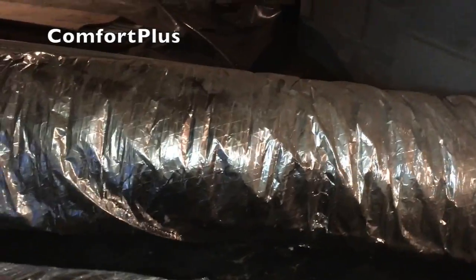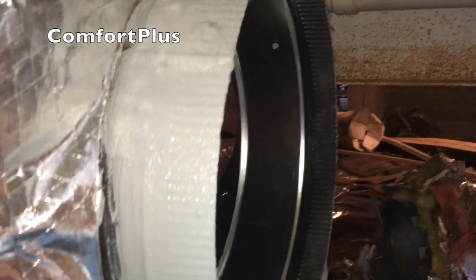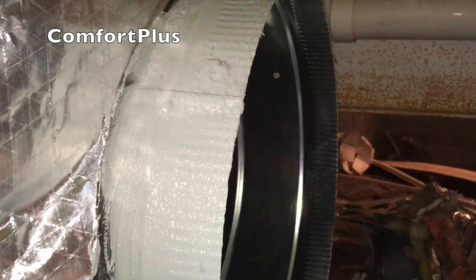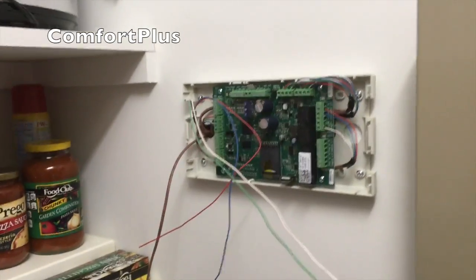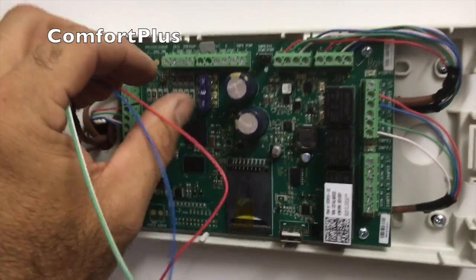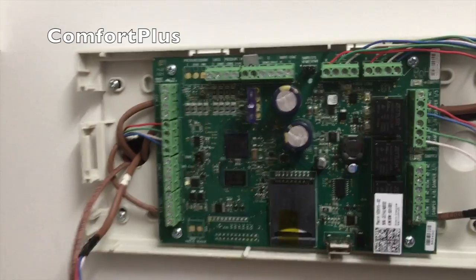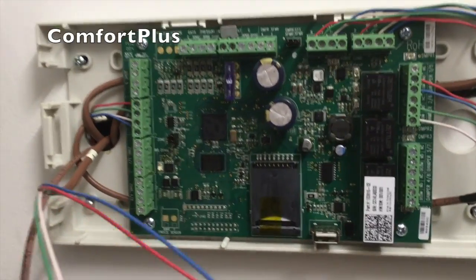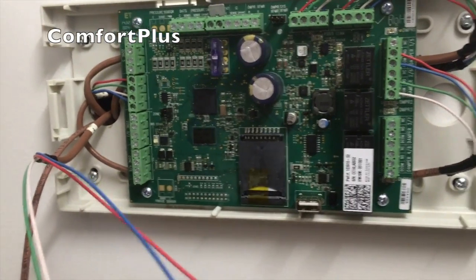Okay, out with the 14-inch return and in with the 16-inch. Got the mastic on it, getting ready to slip it up on there and put some bands and screws in it. Okay, wiring up the damper control module, or the zoning panel as I would call it, here in the, I got it up here in a pantry closet.